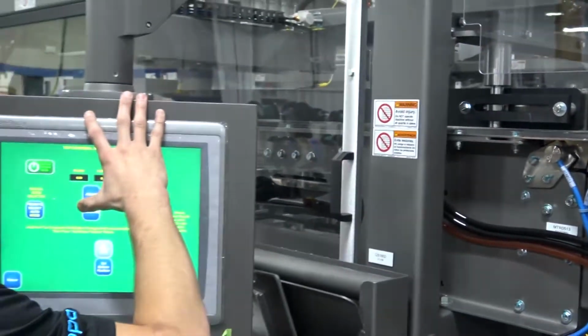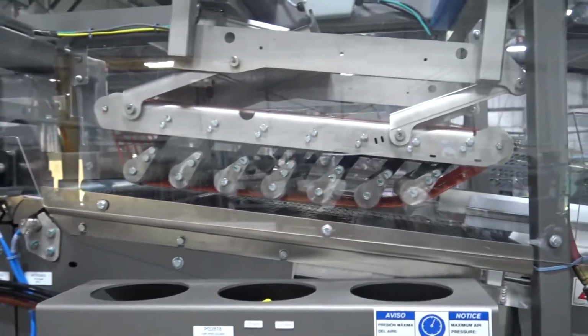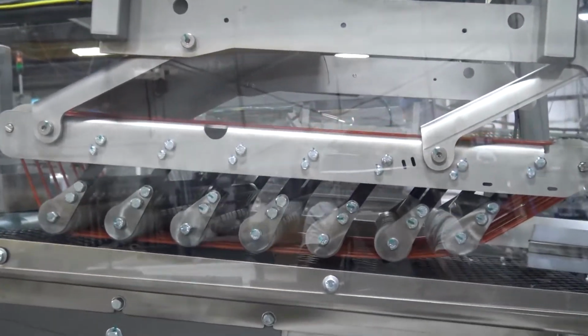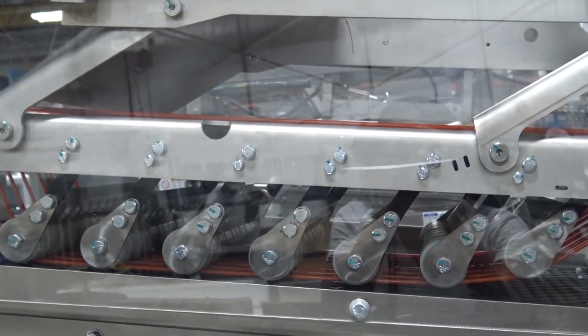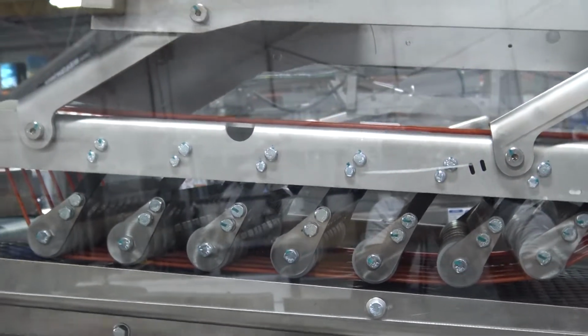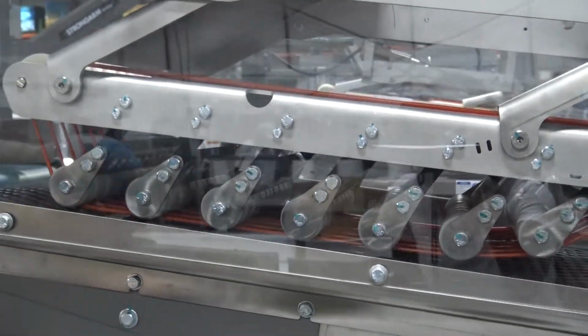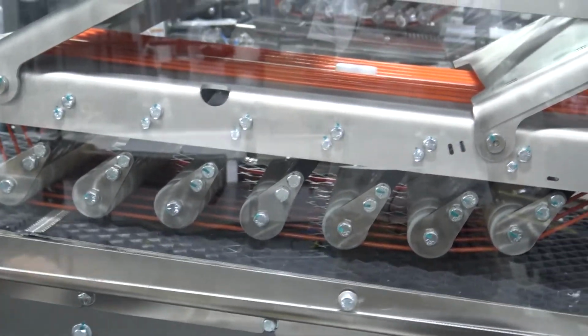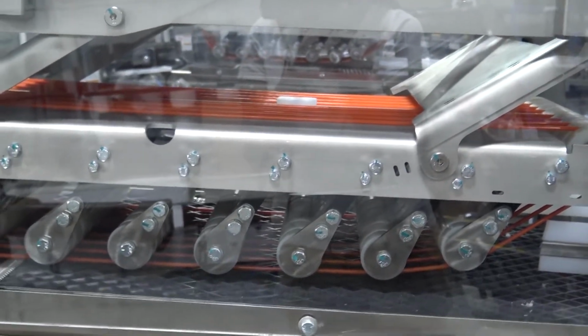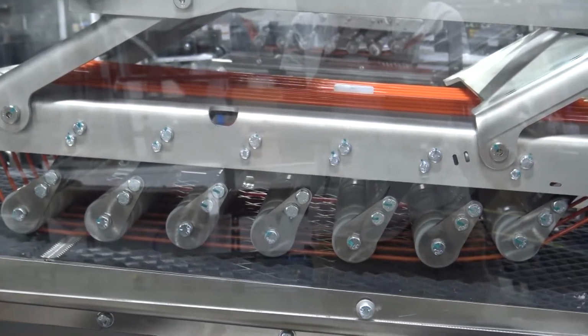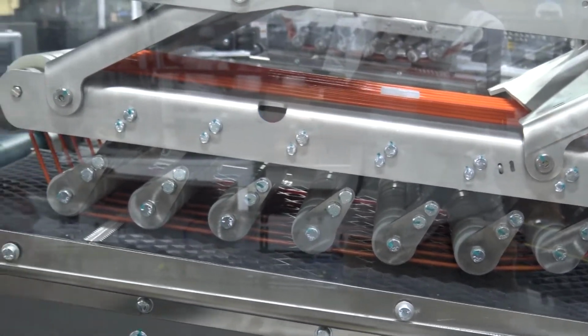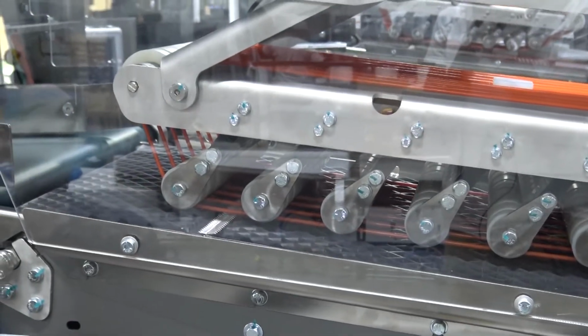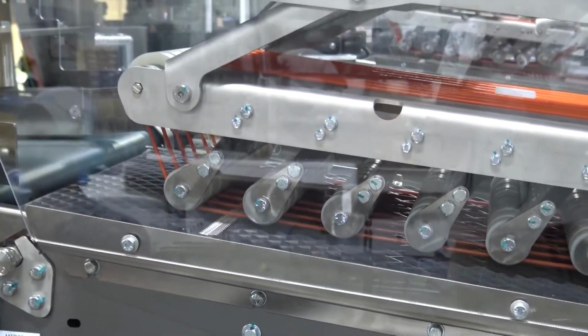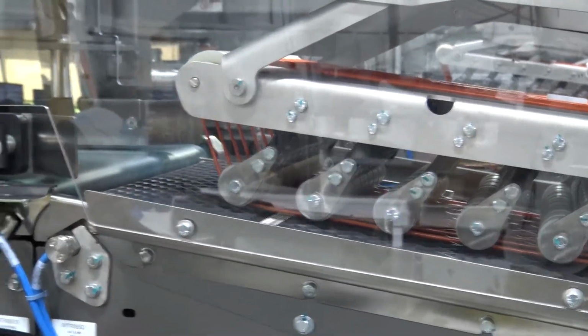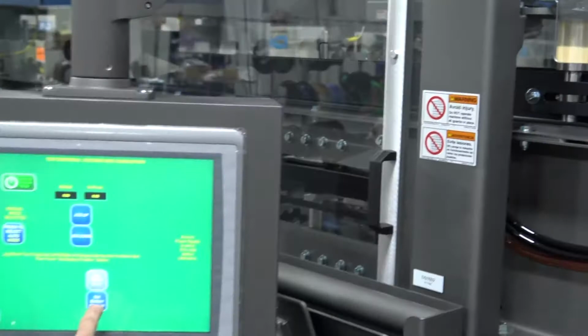So I'm going to jog it down with the push button, and I want to just touch that surface. Right there. I'm just touching that surface. And let's see here. And we're going to consider that the zero position. It might be a millimeter above the surface, maybe 2 millimeters or so. That's okay. It's not a very sensitive position. So I'm going to set the bottom position there on the HMI. So I'm all the way down. I set the bottom position at 0.